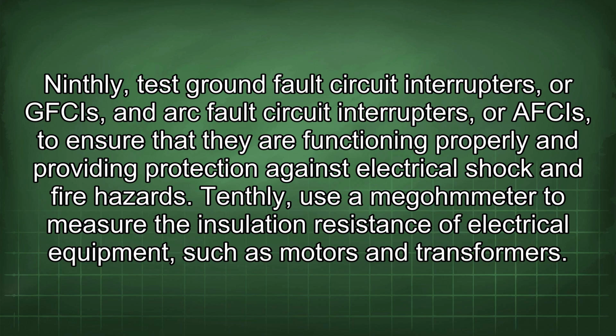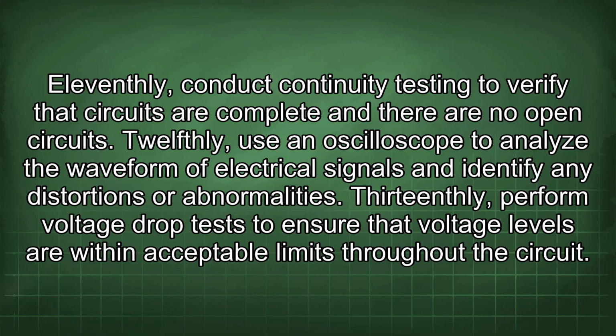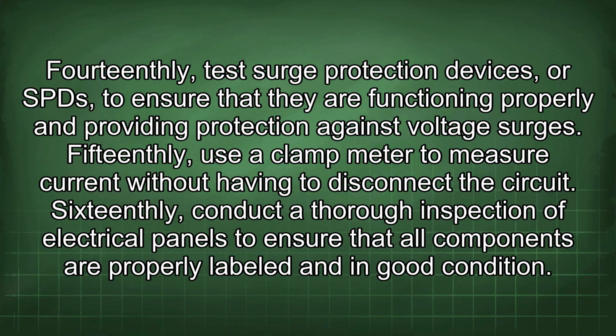Tenthly, use a megohmmeter to measure the insulation resistance of electrical equipment, such as motors and transformers. 11thly, conduct continuity testing to verify that circuits are complete and there are no open circuits. 12thly, use an oscilloscope to analyze the waveform of electrical signals and identify any distortions or abnormalities. 13thly, perform voltage drop tests to ensure that voltage levels are within acceptable limits throughout the circuit. 14thly, test surge protection devices, or SPDs, to ensure that they are functioning properly and providing protection against voltage surges.